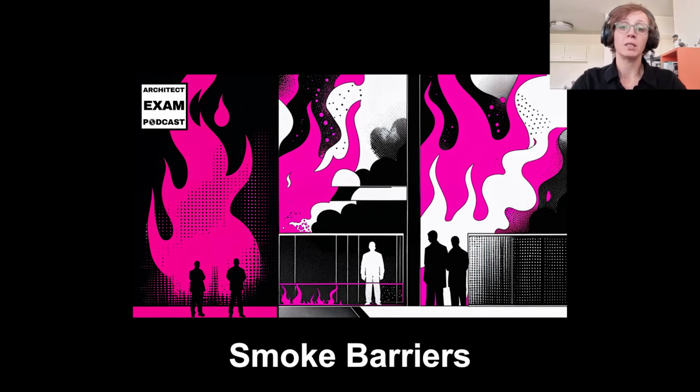From its name, it's a smoke barrier, but it also has another element, which is fire resistance, with that 1 hour fire rating. And as I mentioned, remember that with smoke barriers you can create smoke compartments, and typically you see this in hospital settings. Where can you find this in the IBC? Check section 709 for more information on smoke barriers.